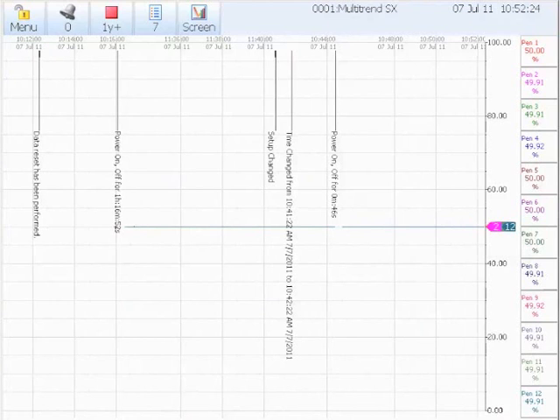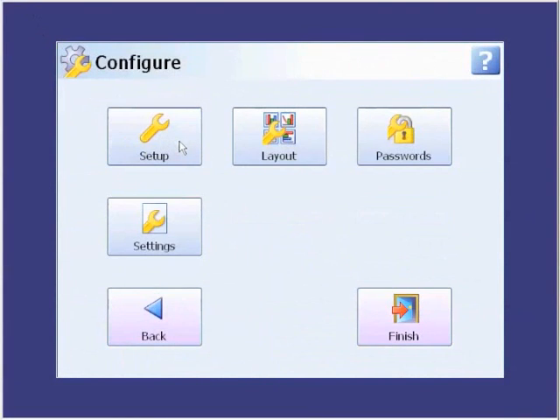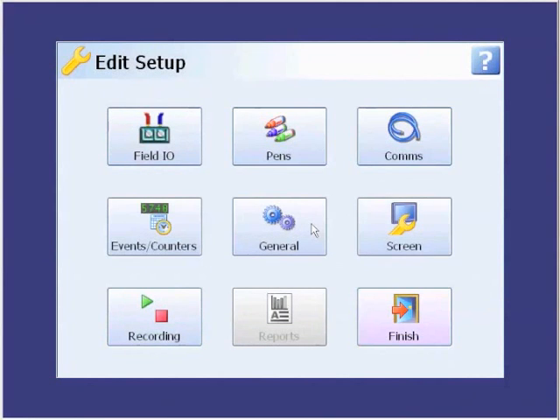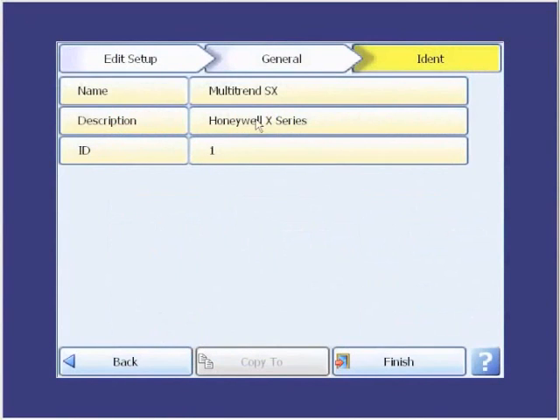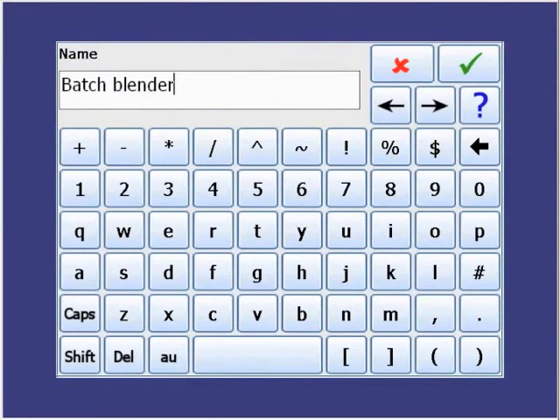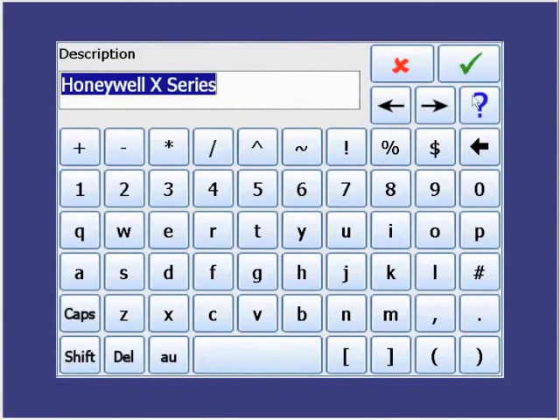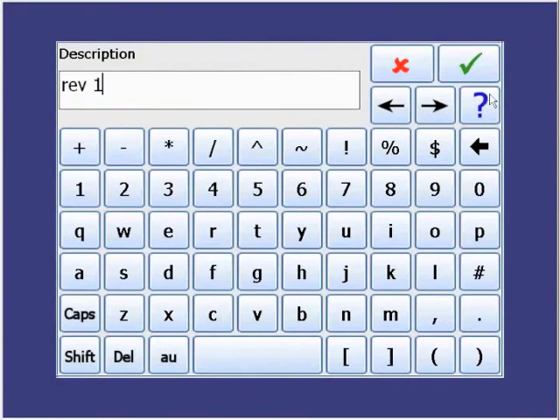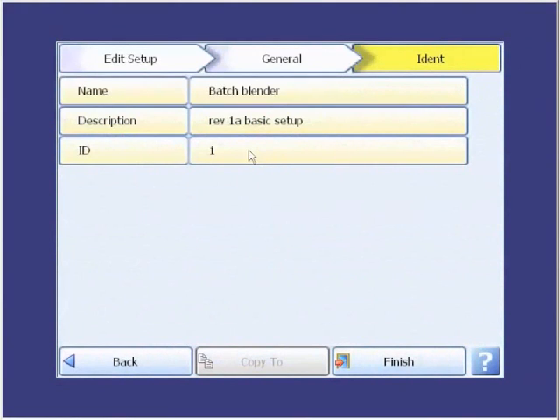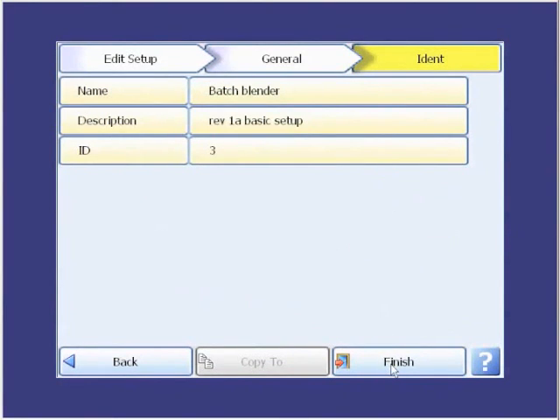The last group we want to configure is the identity group. Again, we configure that by going through the menu as Configure, Setup, Edit, General, Identity. This is where we want to make the name Batch Blender, so we type in Batch Blender. We want the description to reflect the revision — our revision on this setup is 1A, and it's a basic setup. We need to change the recorder's ID number to 3, because it's the third recorder that's going to be on the network. And again, we finish and commit it.